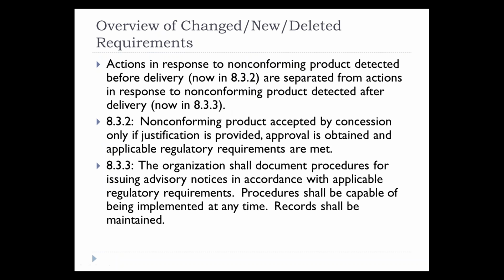In 832 versus 833, we see a separation relating to actions in response to non-conforming product detected before delivery versus actions taken in response to non-conforming product detected after delivery. And if non-conforming product is accepted by concession, it needs to be only in cases where justification is provided, approval is obtained, and applicable regulatory requirements continue to be met. And for products, actions taken in response to non-conforming product detected after delivery, the organization has to document procedures for issuing advisory notices in accordance with applicable regulatory requirements. Procedures shall be capable of being implemented at any time and records maintained.